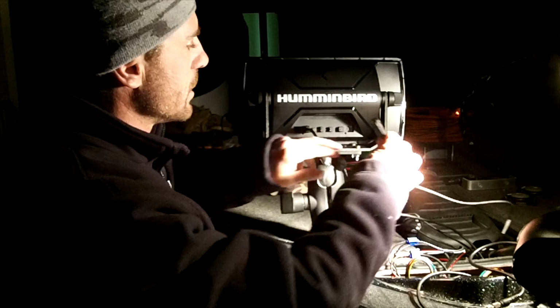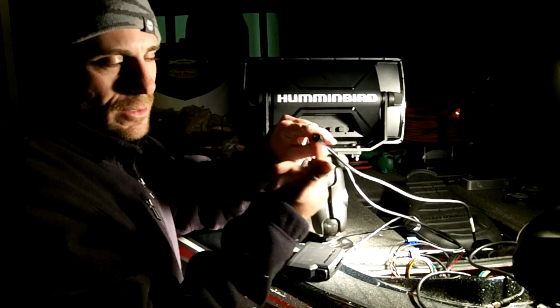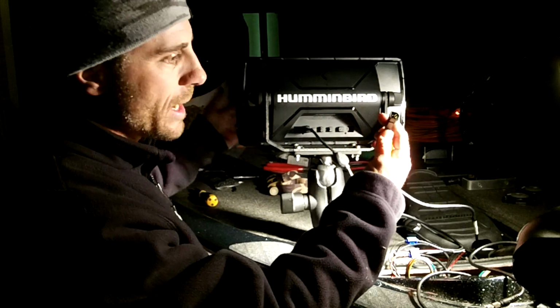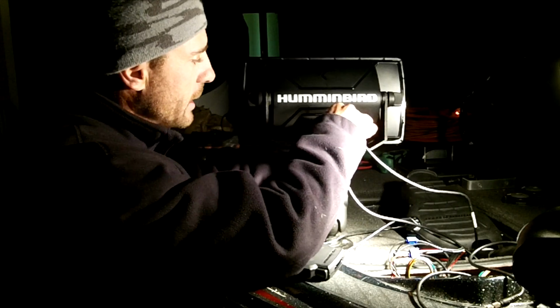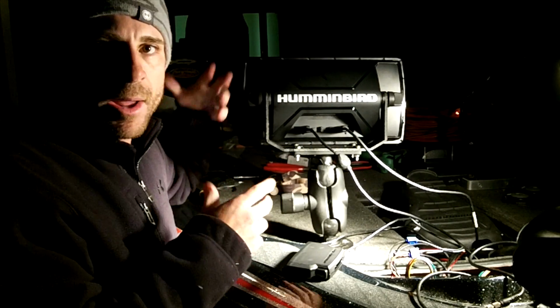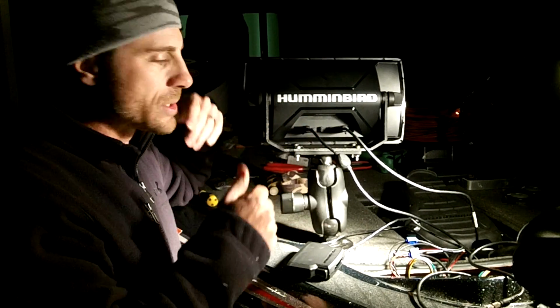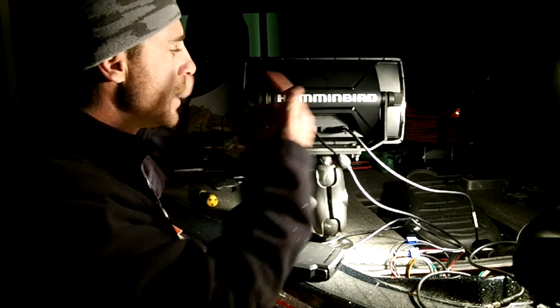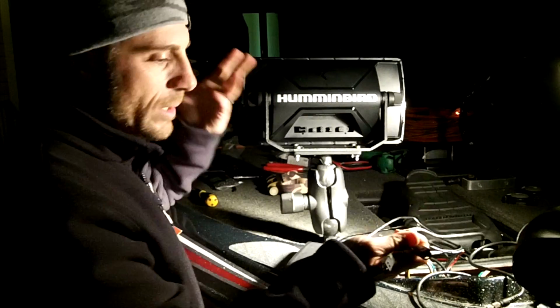Your transducer cable is the only thing that looks like that, it's rounded on top and has a flat bottom. Go ahead and connect that up, then cycle the power on, let it power up all the way. Everything's good, then cycle the power back down. We're going to pull these back off. We did that, everything's good.